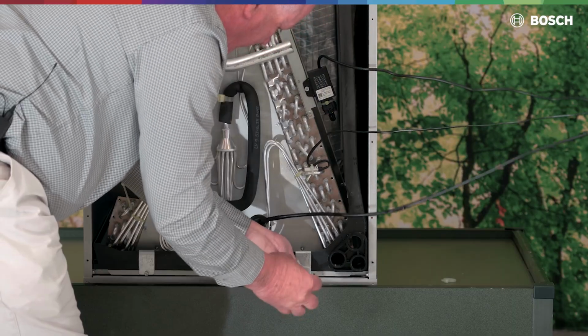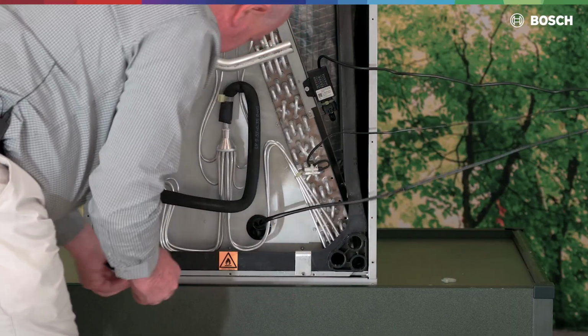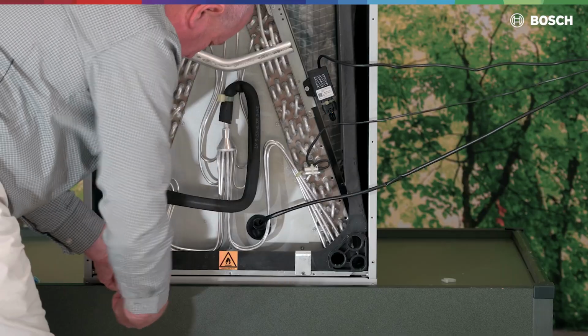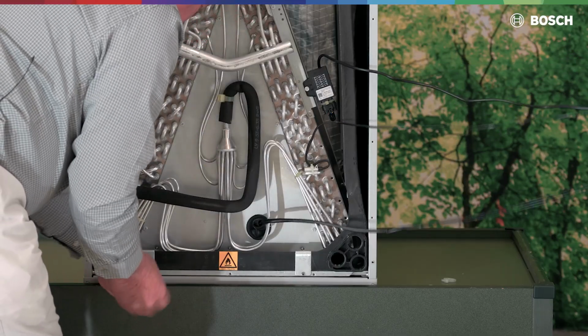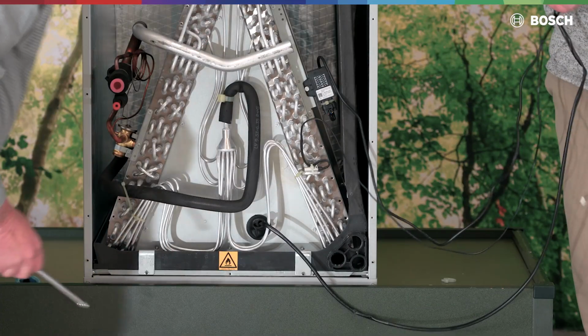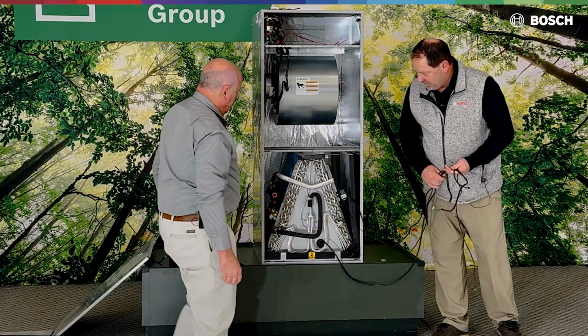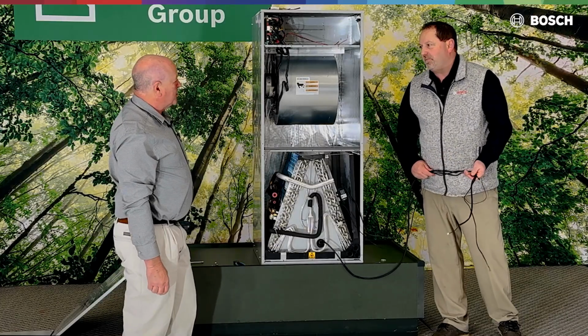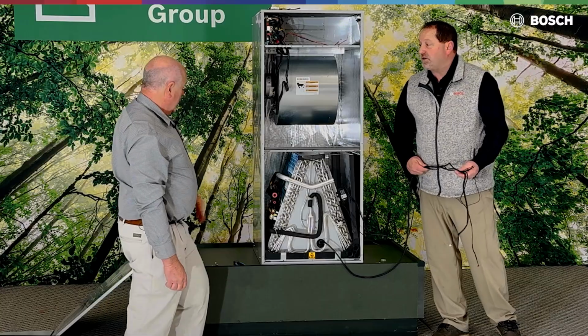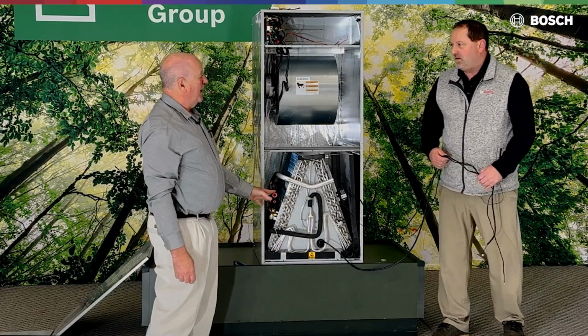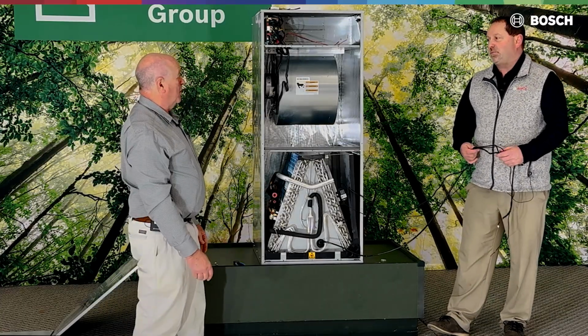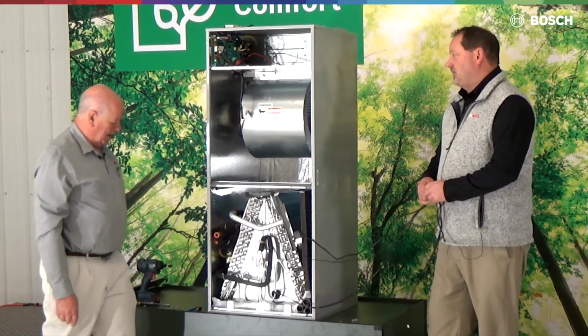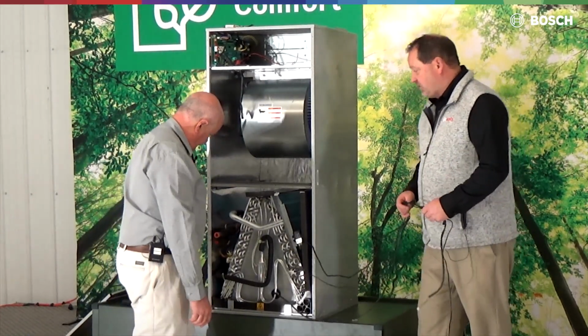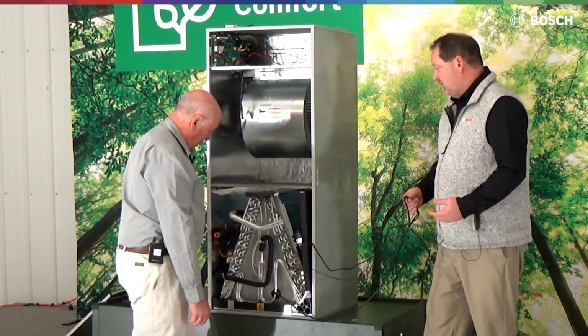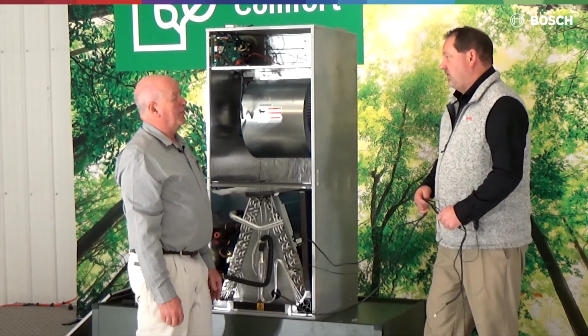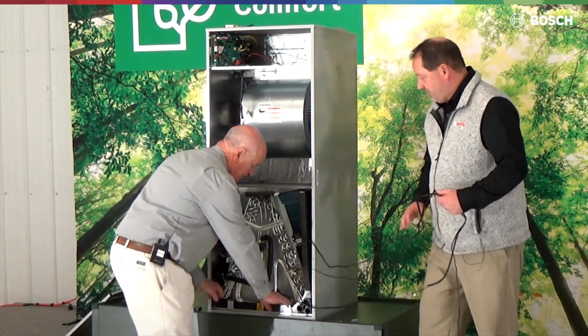Hey Dave, what's that yellow sticker down there? That is an A2L sticker to let you know that this is a flammable unit, so use caution. Okay, so there are some special things I need to do, safety practices and all that good stuff. You know, Chris, one of the things we didn't talk about: these coils do come dry charged with nitrogen. Okay, that's good to know. If you pop these rubber caps out and there's no nitrogen, there could be a problem with that coil, just FYI. Like maybe a possible leak. Possible leak or something at that point. So we may want to try to pressurize it and see, or would we just go get a new coil? Well, that's up to you and your rep, the firm, to make that decision, whether you make the repair or just get a new replacement.